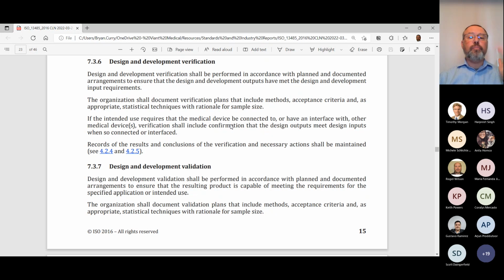What does that mean? It means that you have a protocol. We're going to have a protocol that defines how we're going to verify or validate a specific set of inputs and outputs as it relates to the design of the device. And we're going to document the plans and the acceptance criteria here. We're going to document the statistical techniques that we're going to use to analyze the data that we capture as part of the protocol. And we're going to document the rationale for our sample size.